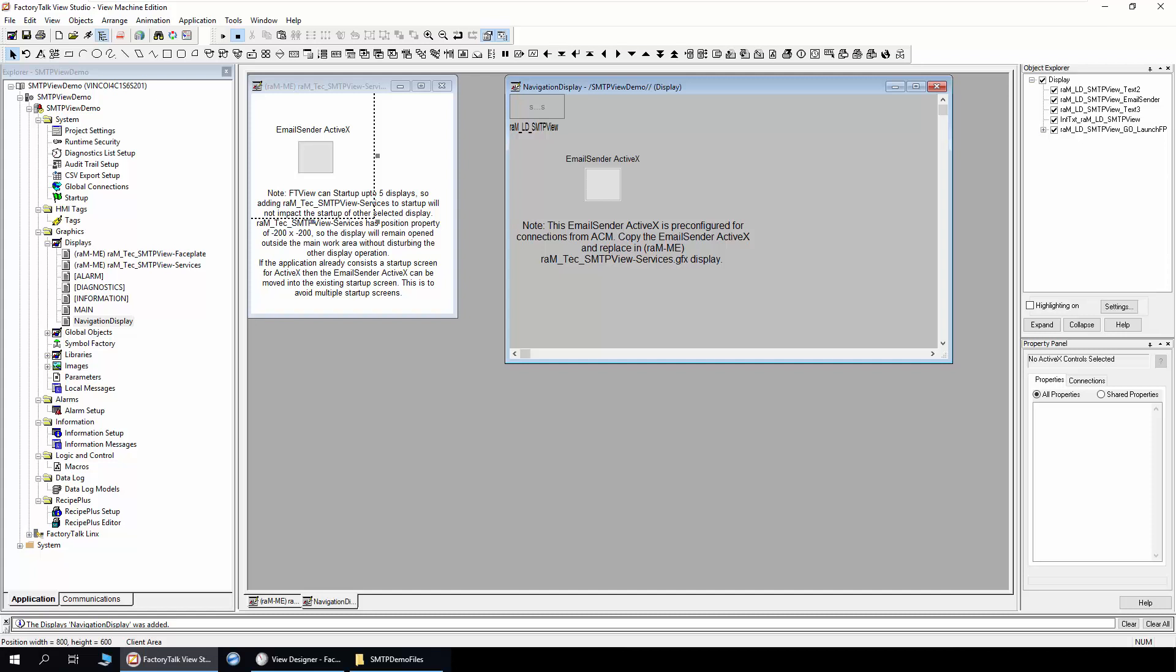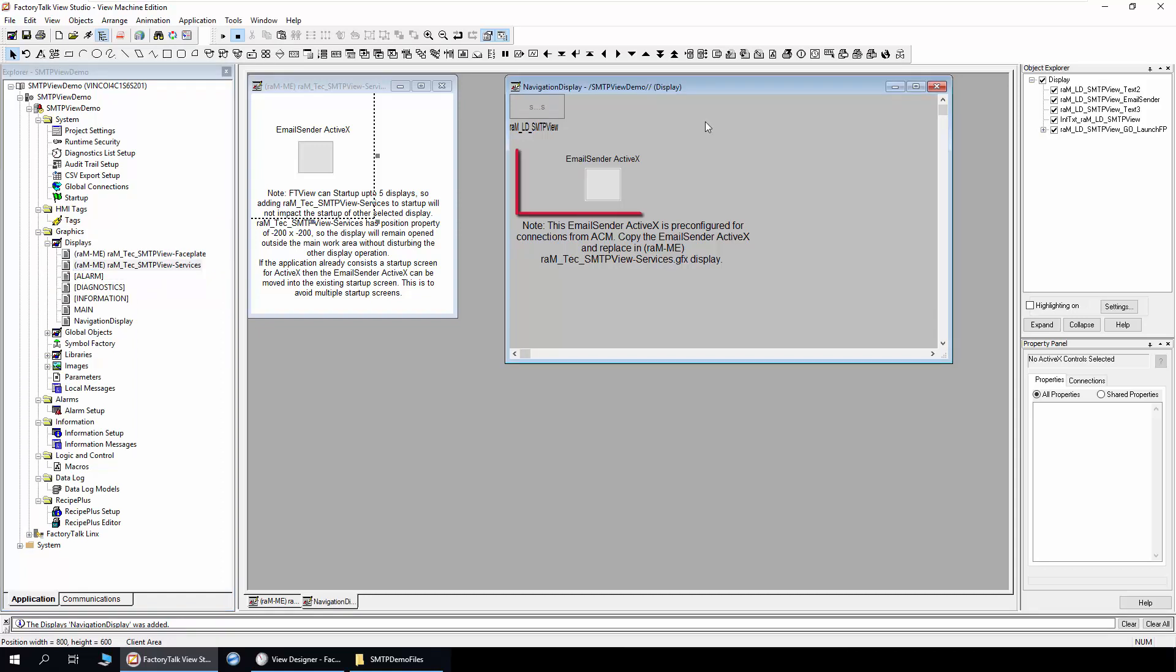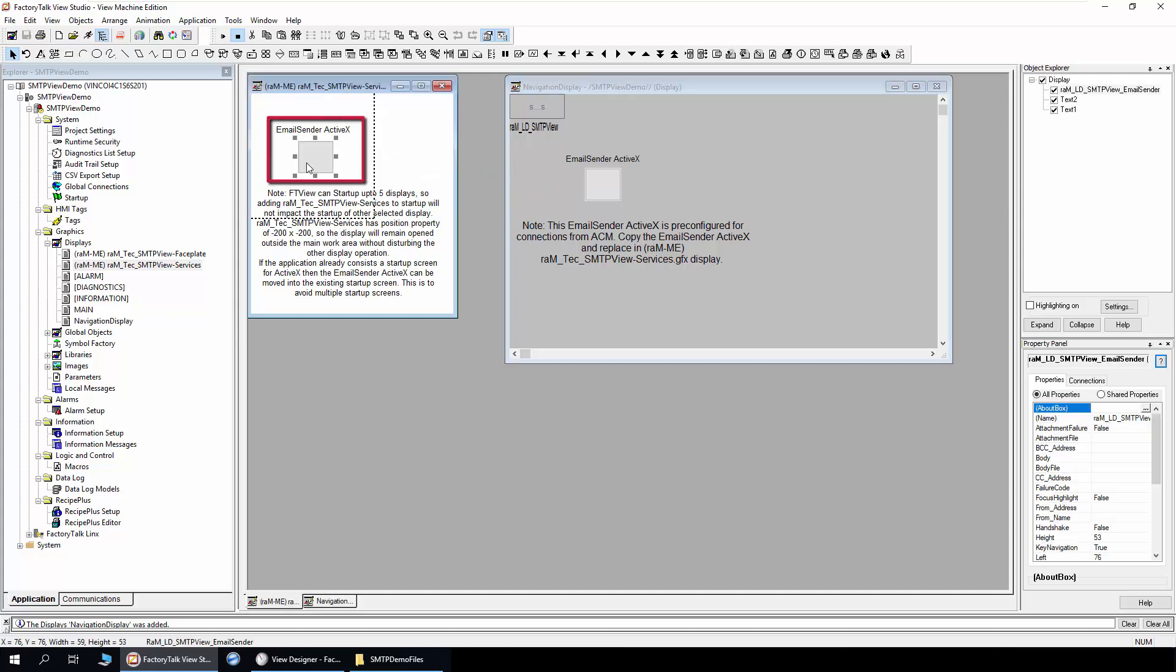I will show you how the email sender feature is configured in FT view and view designer. In FT view, you will get two displays in the attachment. One is the SMTP view face plate, and the second is service display where the email sender ActiveX is placed. A pre-configured email sender ActiveX will be generated from the display section of ACM. Move this ActiveX from the generated display to the service display. The existing ActiveX in the services display can be deleted as it is not configured for the project.